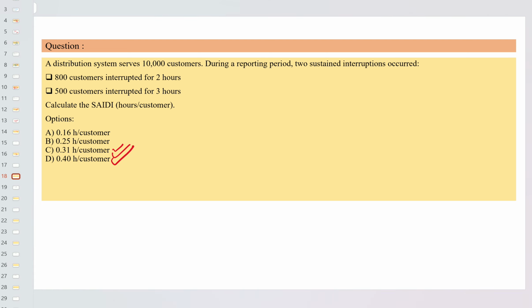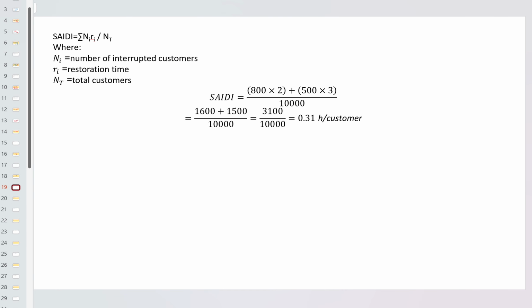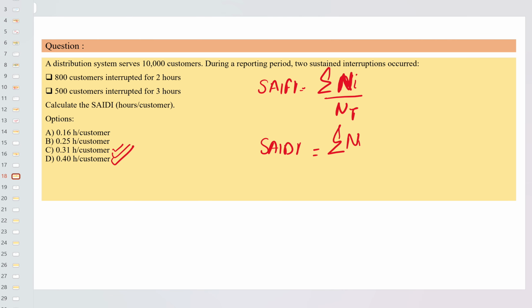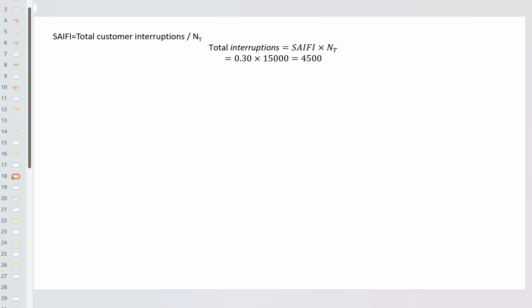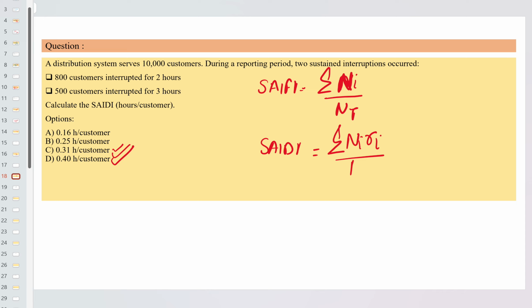Let's see the solution. When comparing with SAIFI, which was just summation of Ni divided by Nt, here time was not considered, interruption time, how much time it got interrupted. But when you compare with SAIDI, by definition, it is summation of Ni times Ri divided by Nt. So when you compare both, here the time frame is also considered. This is more important to understand how this reliability metric is involved, since the time frame of interruption is also being considered.